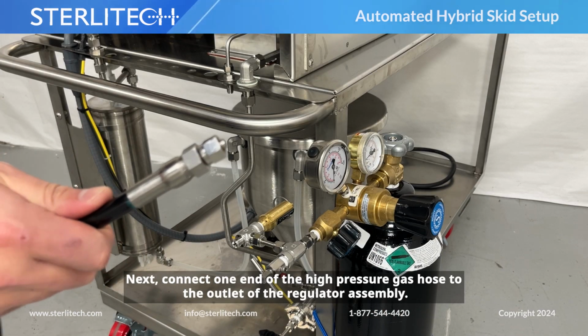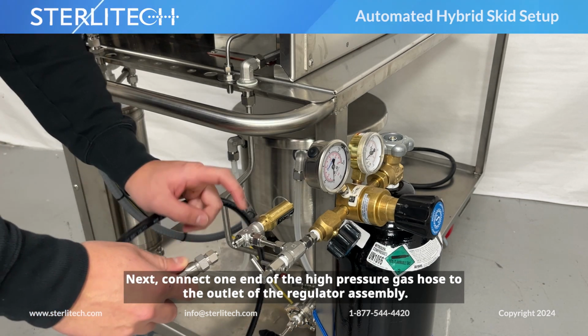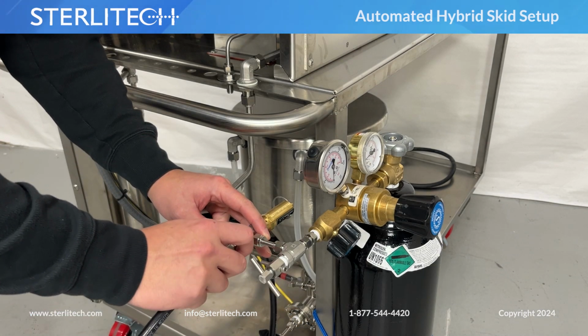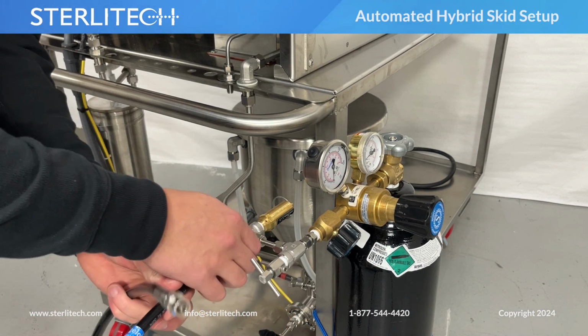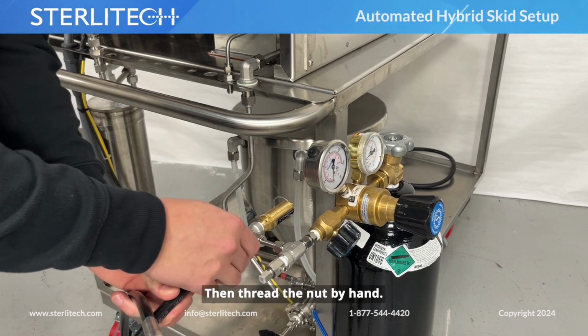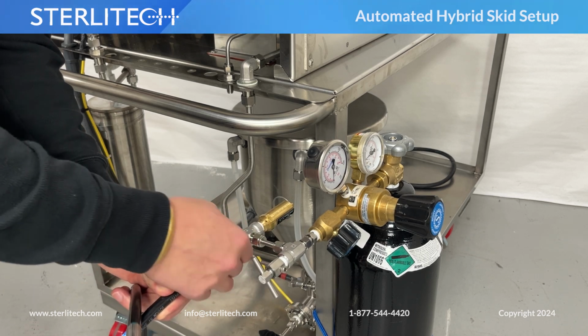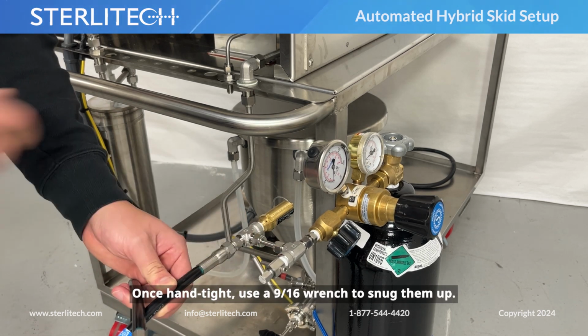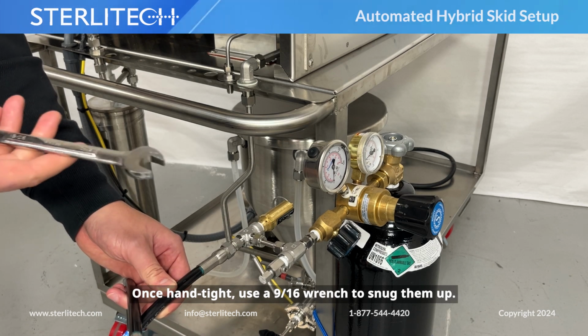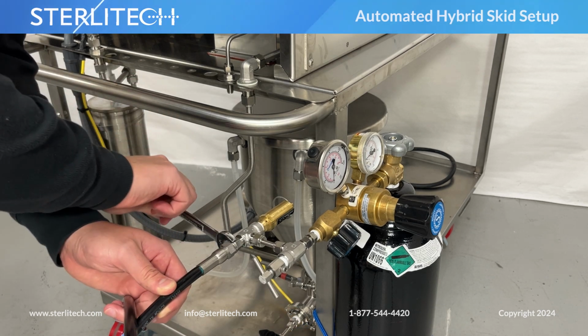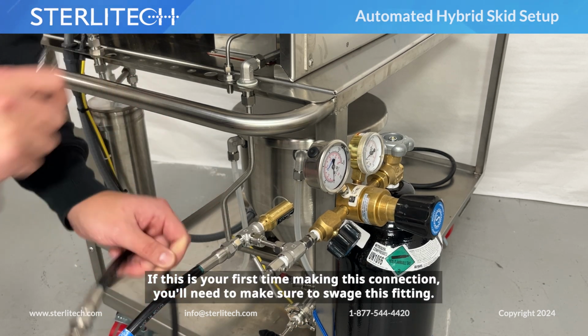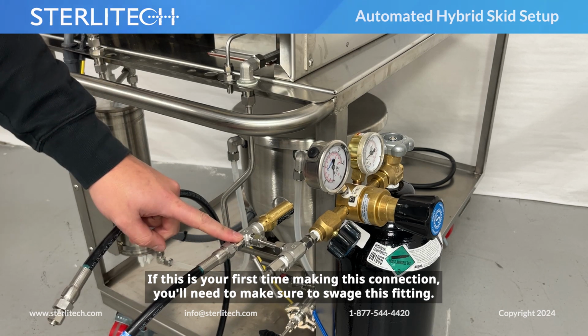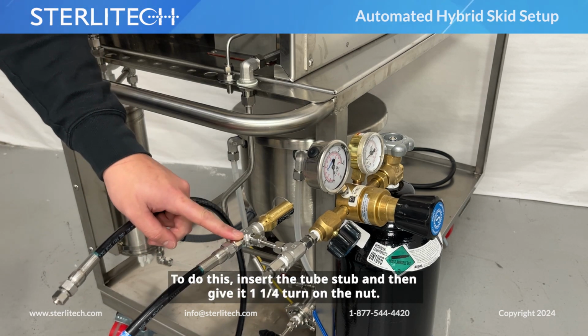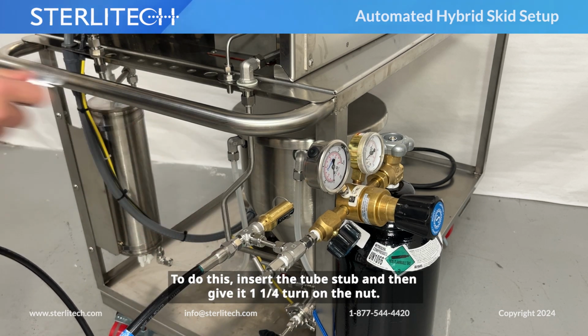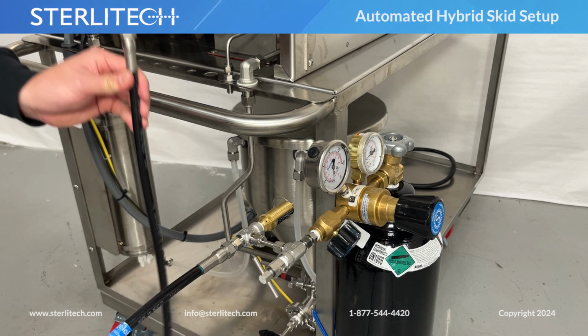Next, connect one end of the high-pressure gas hose to the outlet of the regulator assembly. Insert the tube stub. Then thread the nut by hand. Once hand tight, use a 9/16 wrench to snug them up. If this is your first time making this connection, you'll need to make sure to swage this fitting. To do this, insert the tube stub and then give it 1 1/4 turn on the nut.